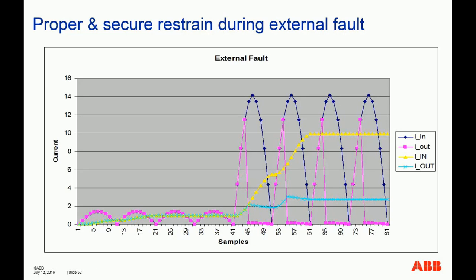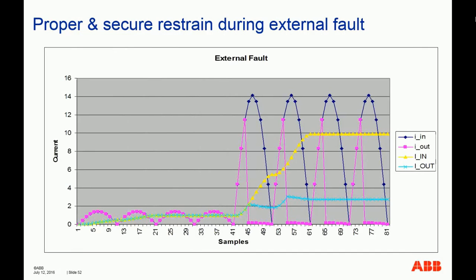And actually, when the fault happens, the internal and external currents rise at the same time together, as before. So they rise at the same time. But after, let's say, 10 milliseconds, the CT starts to saturate, and they start to pull apart, as you can see here. Similarly, you can see the instantaneous values start to pull apart. They stop coinciding with each other. And then this is when the relay knows that this is an external fault. It's not an internal fault, it's an external fault.